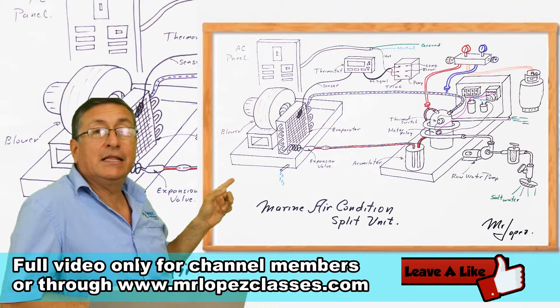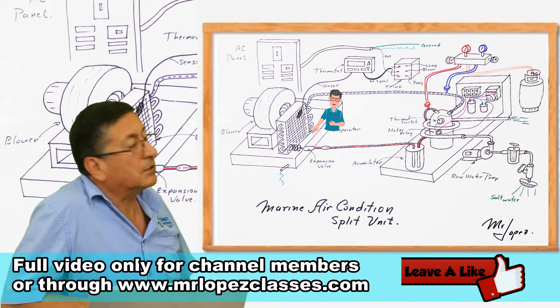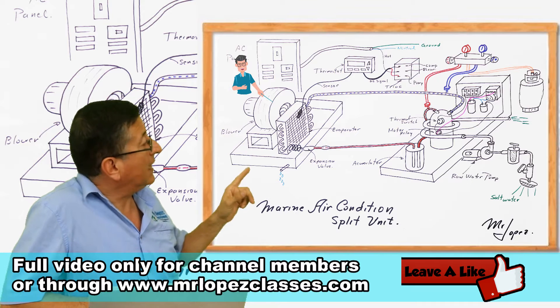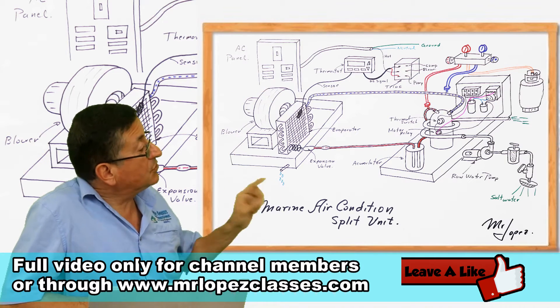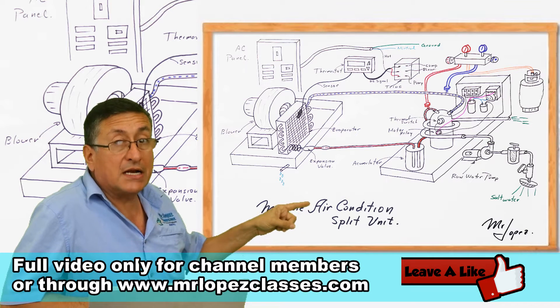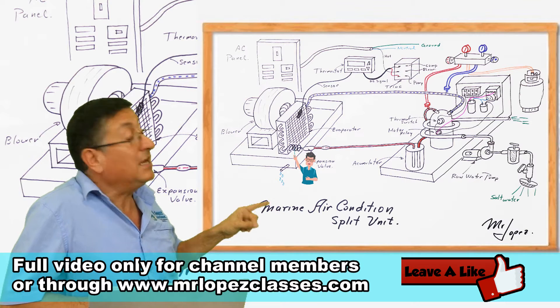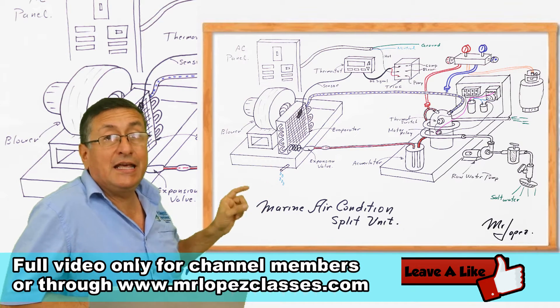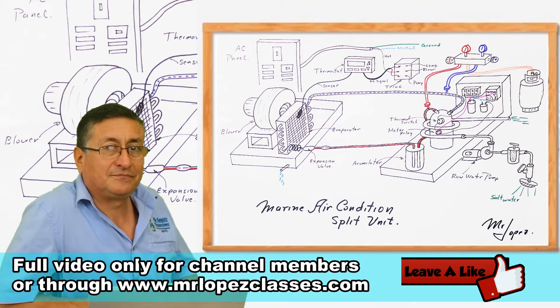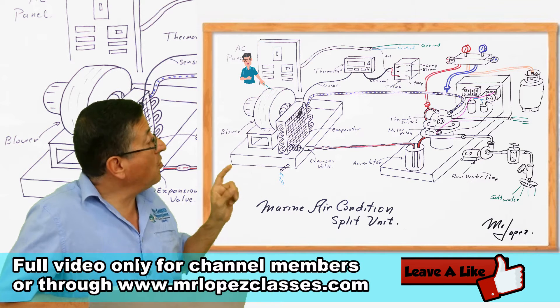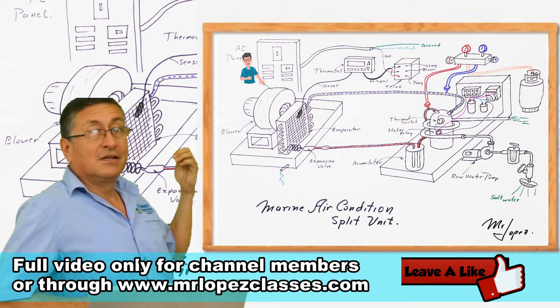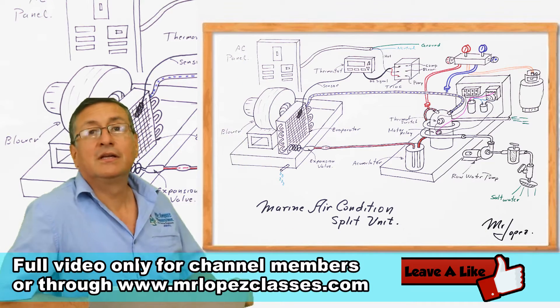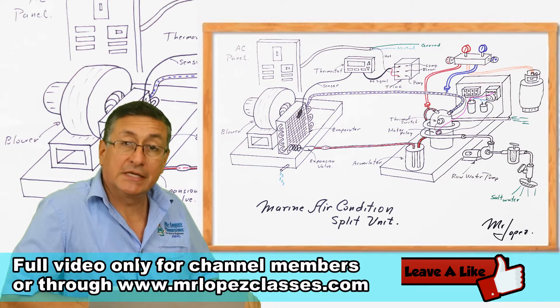In the evaporator, we have the evaporator coil and the fan. The coil of the evaporator — remember that as soon as the refrigerant passes through the dryer and the capillary pipes, immediately the pressure and the temperature decrease dramatically. Those pipes internally in the coil of the evaporator are practically frozen. When the fan forces the flow of air from the inside of the room through the coil, on the other side at the output, you have cold air. This is the evaporator.